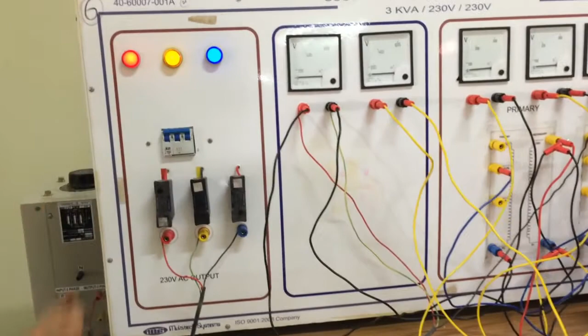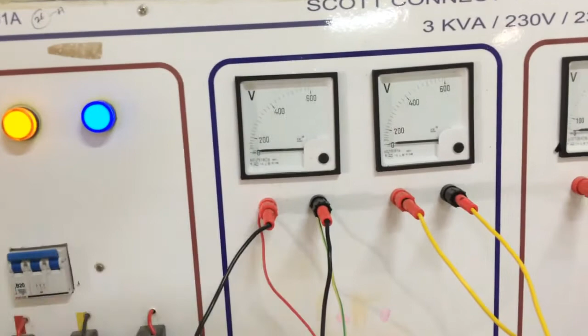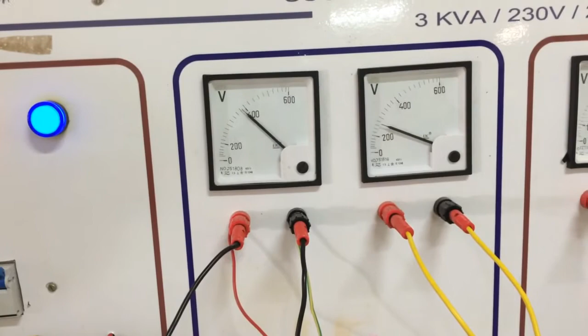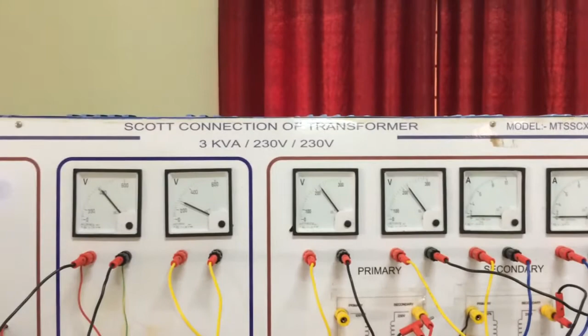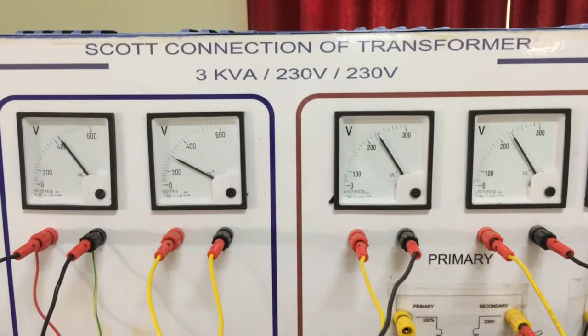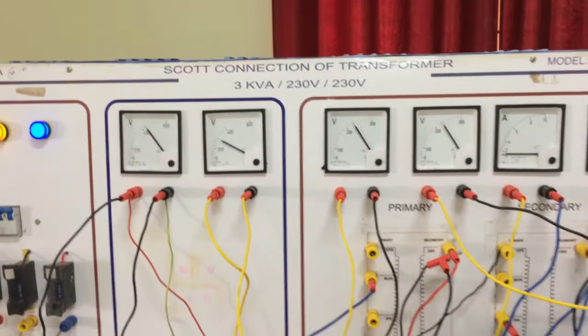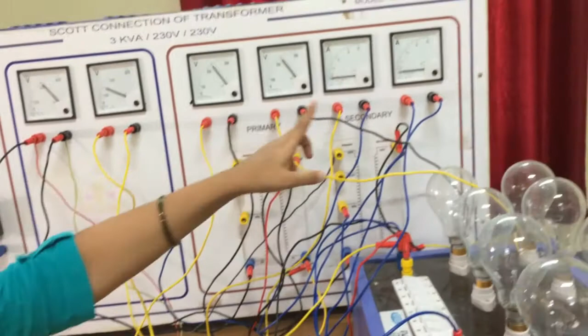Now let us put on the supply, switch on the MCB, and slowly vary the variac until the voltage reaches 415 volts, which is the rated voltage of the three-phase transformer we are using here. You can observe this is the voltage across one of the phases, and this second voltmeter is the voltage across the other phase. This voltmeter reads the resultant voltage across the two phases. These are the ammeter readings, each connected in series with one of the two phases.